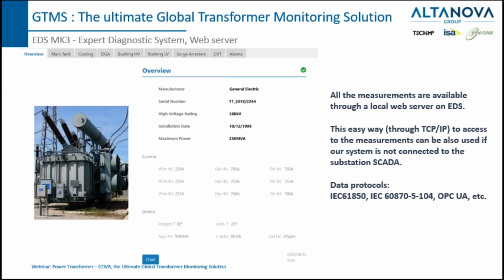Regarding the web server, you can have here an example of the homepage of the web server that is integrated in the EDS. This is the easy way to access all the measurements that we can detect and that we can have in our system. And we can configure this web server according to the project layout. You can see here several tabs. You have an overview with the generic information of the transformer, then main tank, cooling, for example, DGA, bushing, high voltage and low voltage side, surge arrester, CT, CVT, and alarms. I have some other examples in the following slides. Just to mention that several data protocols are available, IEC 61850, 104, OPC UA, and others.